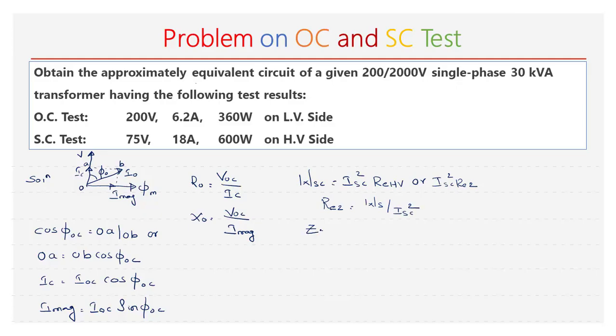The total equivalent impedance referred to the secondary, ZE2, is equal to the voltage during the SC test divided by the current during the SC test. Next, we can find the equivalent reactance referred to the secondary as XE2 is equal to the square root of ZE2 squared minus RE2 squared.